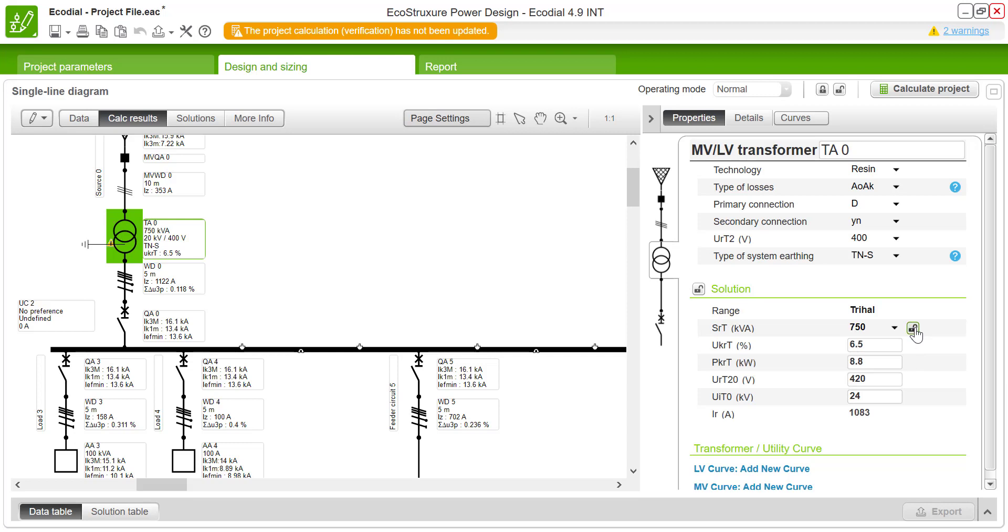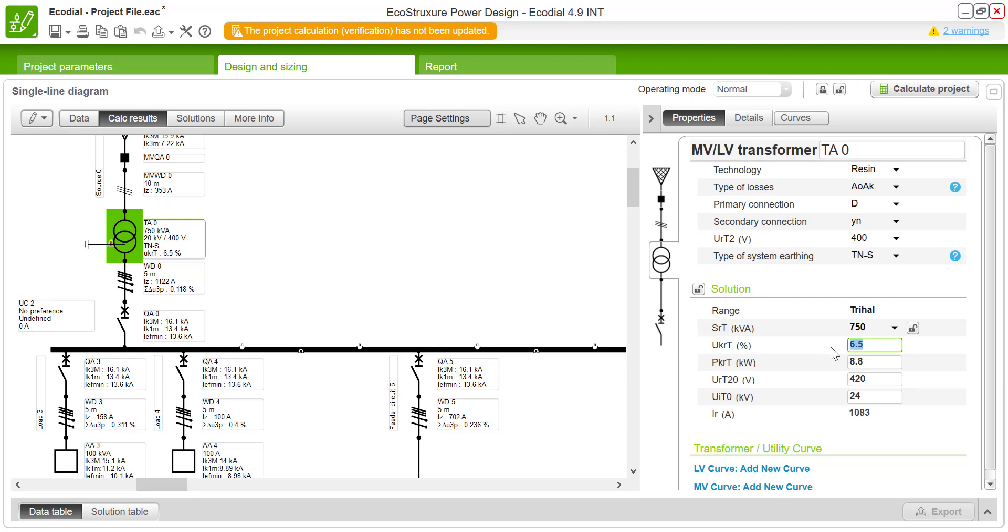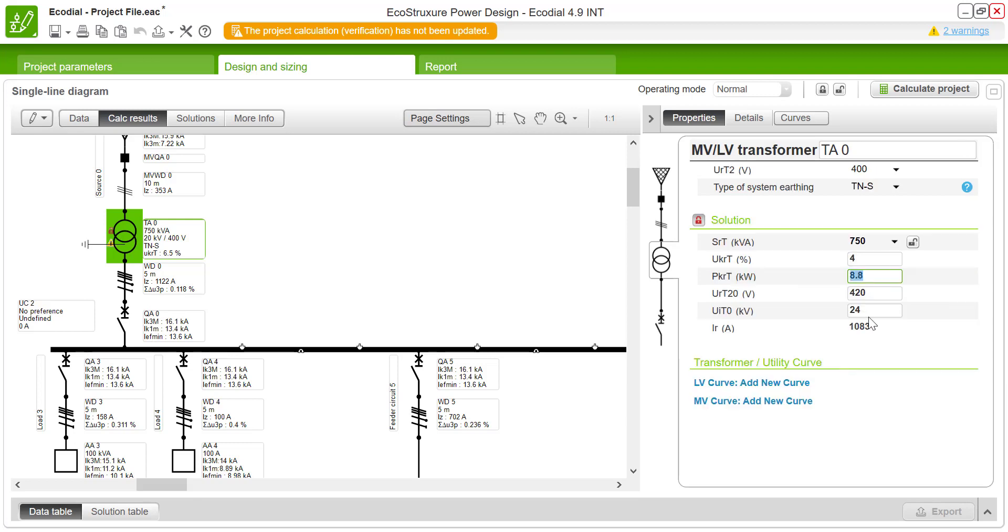Taking a scenario where you want to customize the transformer characteristics—for example, short circuit voltage for the rated current and the power loss value. I'm going to change this value to 4 and the power loss value to 6 kilowatts. After the calculation, I will show you the difference in results, and it will be clear that the given inputs are considered for the calculation.